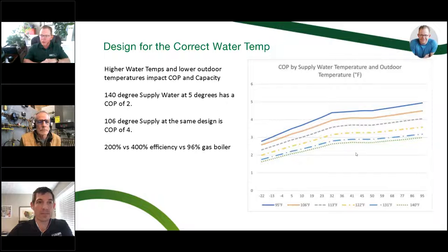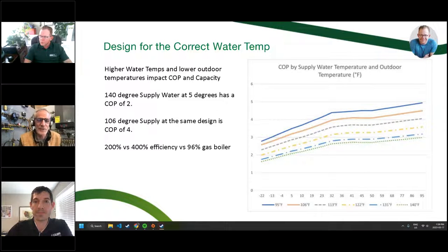The last thing you want to do is put in a heat pump, which is going to cost more than a boiler, and inadvertently give them something that should be 400% efficient, a COP of 4, that in fact has a COP of 1.5 or 2. As a guy who's done this for 2 decades, I unfortunately do have to go to jobs and have that difficult conversation: there's nothing wrong with the piece of equipment, it's everything around it. Bob, anything to add to that? No, it's all about the design. We keep saying that in a lot of different ways, but there's no way around it. Yeah, we need to be very focused on design.